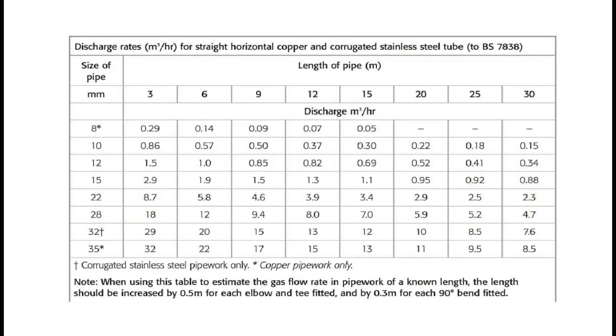Here we go. This is the chart in the Viper book, section I, page I-5. We've got copper pipe and 3.5 meters of copper pipe, so the first thing we do is look across the top to calculate our length. 3.5 meters sits in between three and six on this chart. Three is too small, so we simply go up to the next number and calculate it from there. We're going to calculate this from six.